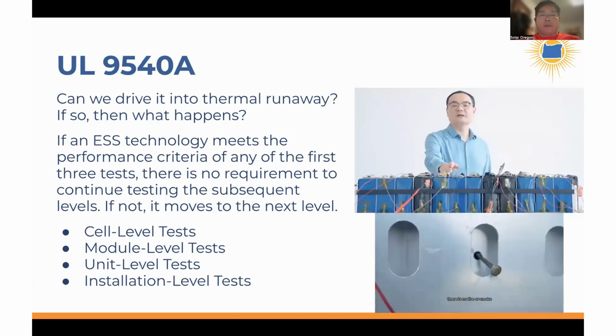So 9540A is not necessarily a test standard, but a test procedure to try to see what happens when you try to induce a thermal runaway. So by either damaging the cell - like if it gets punctured with a nail - what happens to the battery? Does it vent a lot of gas, and is that gas going to be a problem, or is it going to explode?